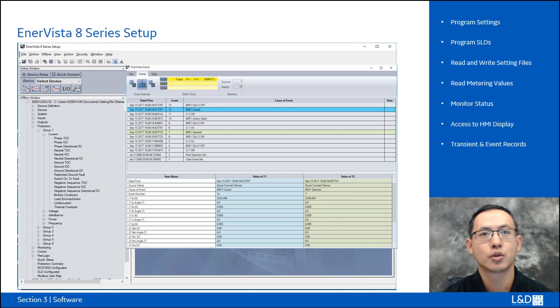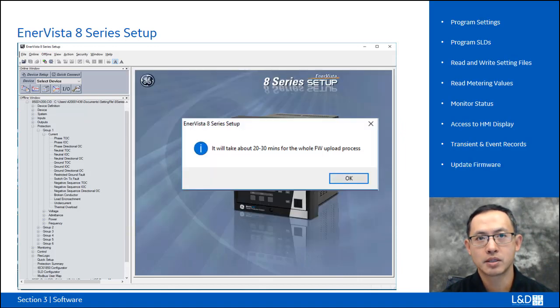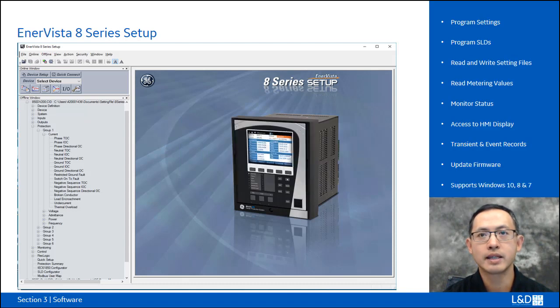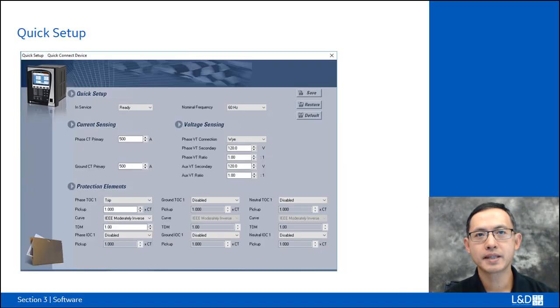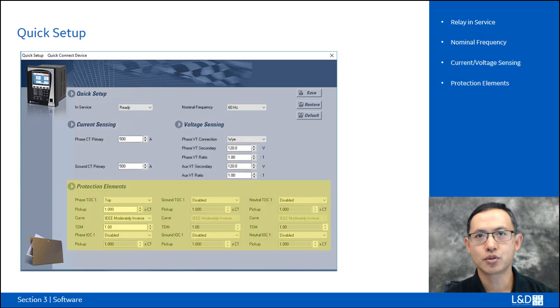It can also read pre-fault transient and event recorder for post-mortem analysis. It can upgrade 8 series firmware, and the 4 types of relay share one platform firmware. EnerVista 8 series setup works under Windows 10, Windows 8, and Windows 7. Quick setup allows the user to configure the main settings from different screens in one common window: relay in service, nominal frequency, CT and VT sensing setup, and configuration of the main protection function in each application.